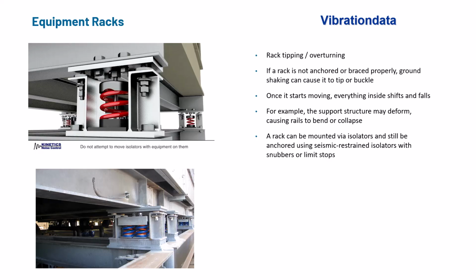The rack can be isolated, mounted via isolators, and still be anchored using seismic restrained isolators with snubbers or limit stops. So yes, we want a soft mount system, soft springs, but we also need some devices in place to limit the displacement, because we don't want the rack to overturn.